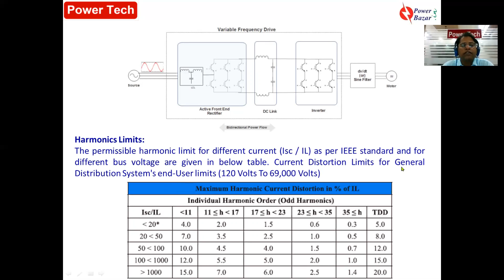So I will advise that because of this pollution, your whole plant system is also getting affected. Your equipment is failing, you are getting nuisance tripping, and your energy consumption goes up because of heating. So kindly put in an active filter or passive filter or any good filter. That means you try to treat this nonlinear load. Similarly, if I find voltage distortion is also around 10%, then it is also polluting the grid end. So I need to take some action, put in some active or passive filter, to nullify the effect of harmonics.